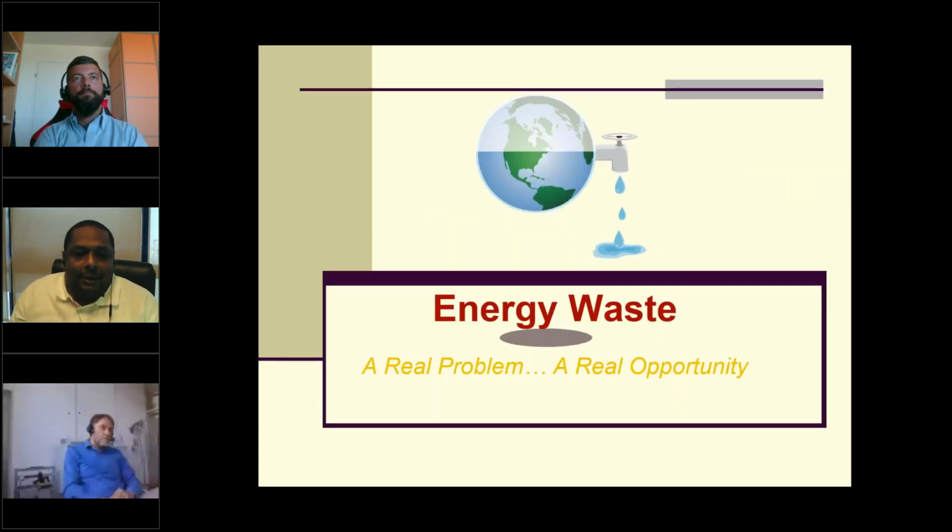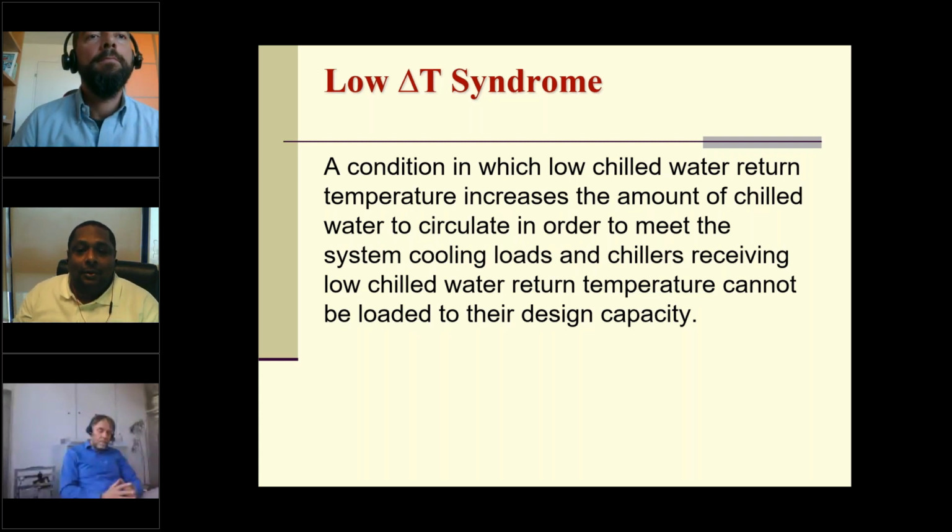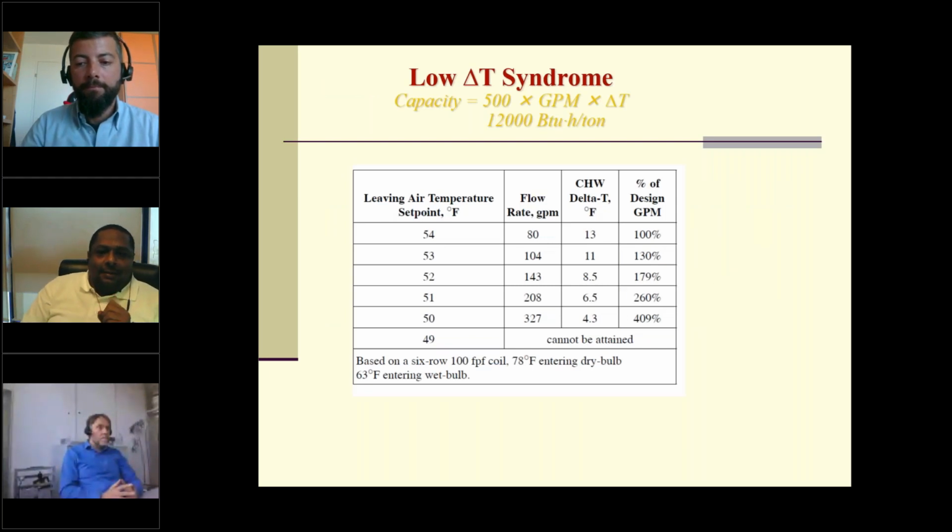Energy is very important in our environment, in our day-to-day use, and this seminar today is touching one of the biggest problems we are facing in our industry, which is the low delta-T syndrome. Low delta-T syndrome is a condition in which low chilled water return temperature increases the amount of chilled water to circulate in order to meet system cooling loads, and chillers receiving low chilled water return temperature cannot be loaded to their design capacity.